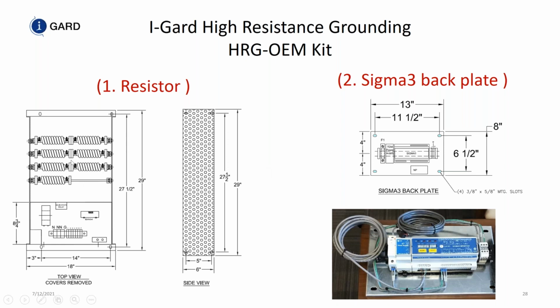So you need a resistor to limit the fault current, and you need a relay to detect the presence of a fault. This one is a Sigma, so Sigma 3, so it can actually detect the presence of the resistor and open and short circuit of the resistor, and you have a display module on the front of this. So this is as big as it gets. 13 inches by 8 inches for the OEM kit. You have a resistor which you can place somewhere.